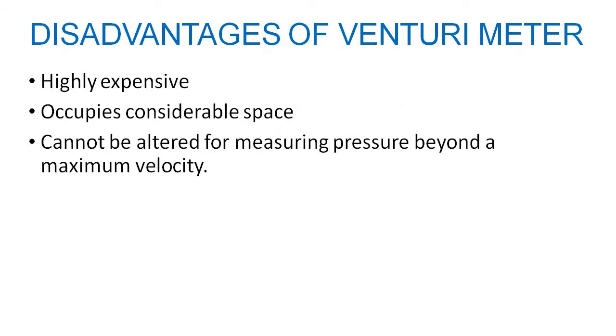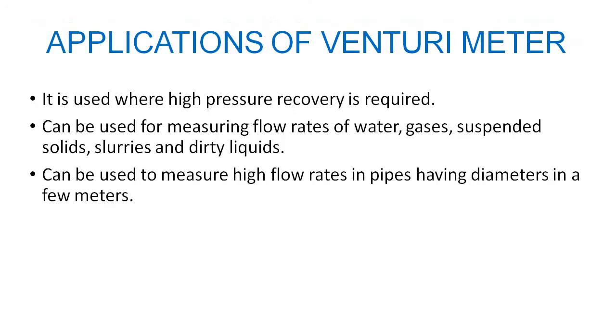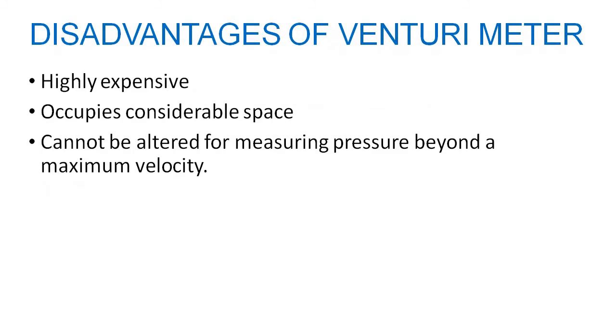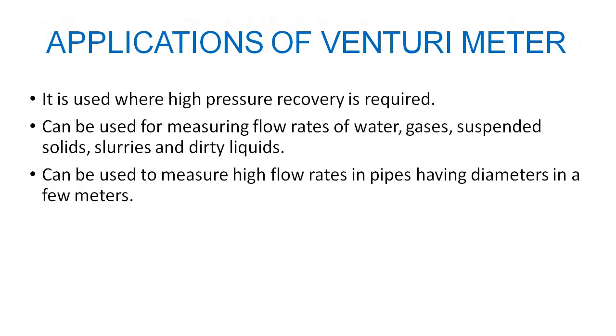Now disadvantages. Highly expensive because this cross section is quite difficult to make. Occupies considerable space. Cannot be altered for measuring pressure beyond a minimum velocity. If the velocity of the flow is very less, there is no pressure difference that will be generated. If you want to measure the pressure, then the flow must be typically high.